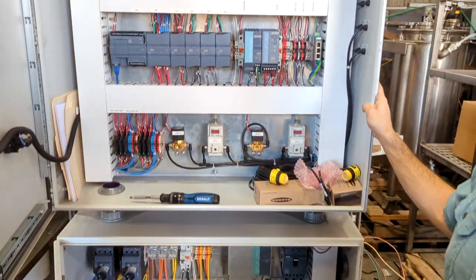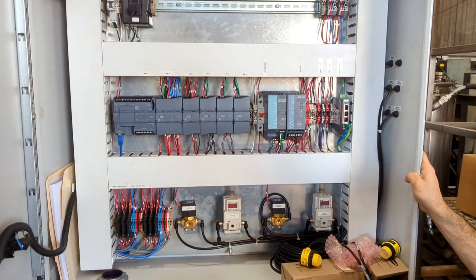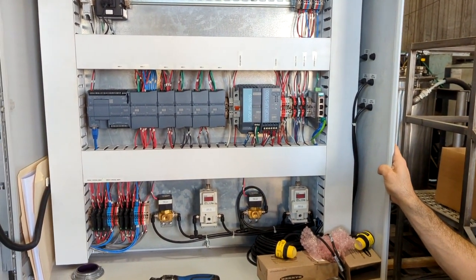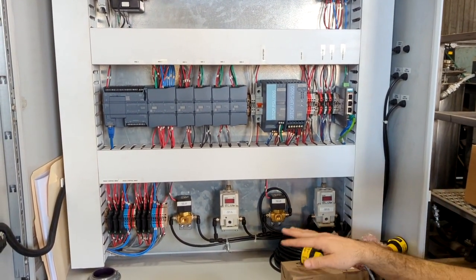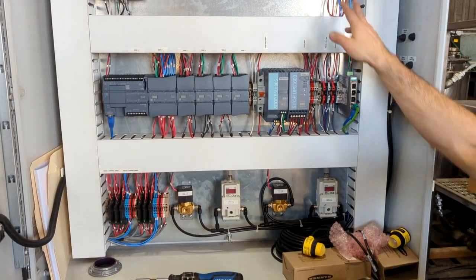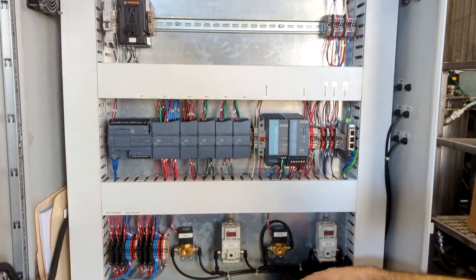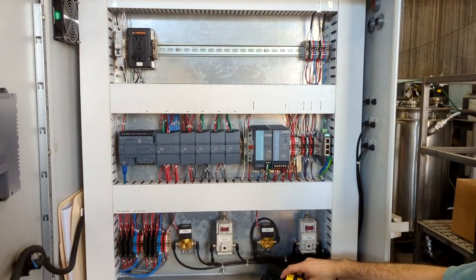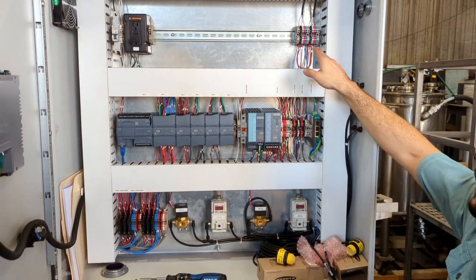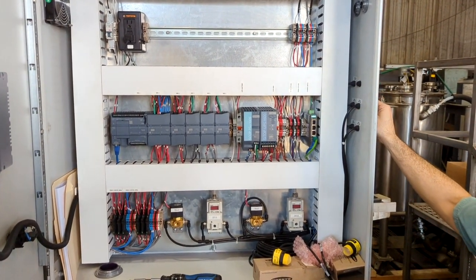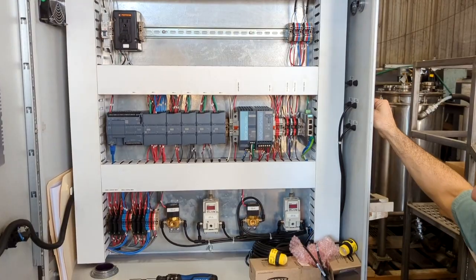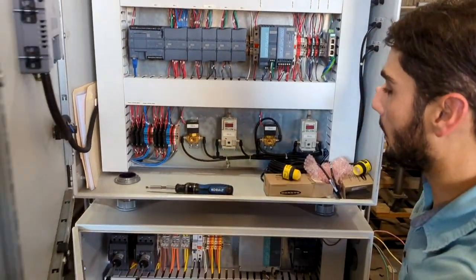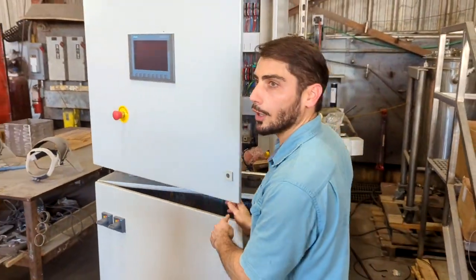don't incorporate Ethernet, but we have it here. No problem. We're using Profinet to communicate over. And these are all of our actuator controls. Our field connectors are pre-wired, so the electrician, when he gets out in the field, knows exactly how to reconnect it to minimize any downtime that's going to go along with hookup. And that's our control system that we have here, ready to get shipped to a customer.